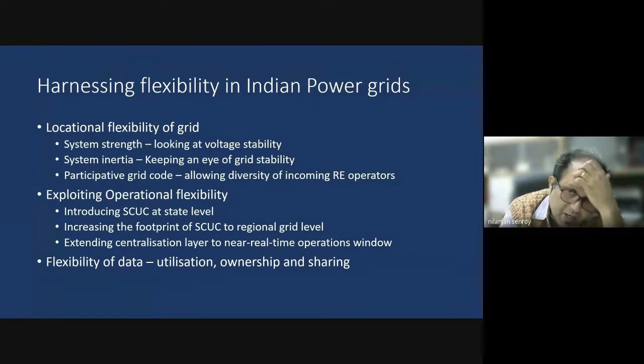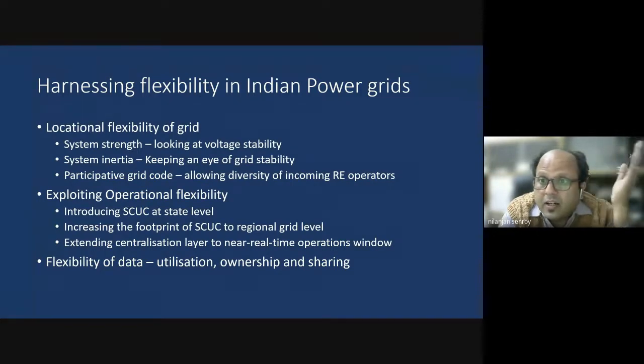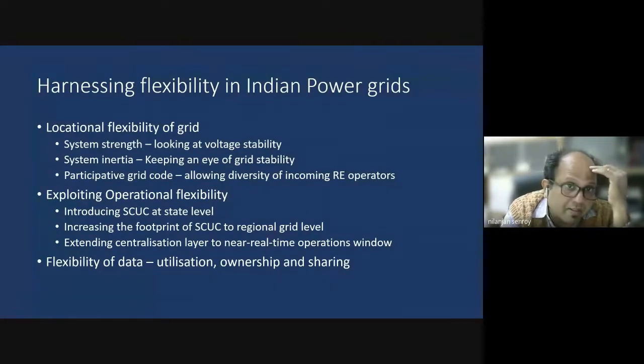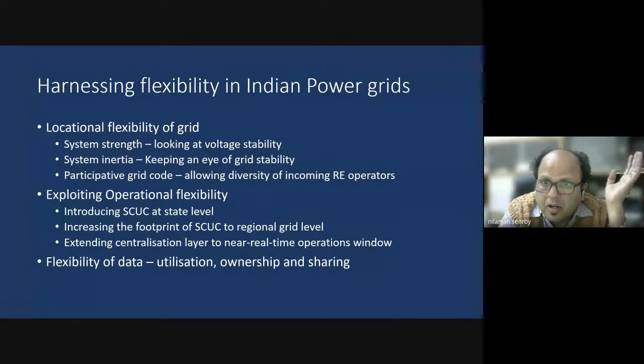Therefore, it is recommended that an accurate mapping of available system inertia should be carried out periodically, and you can reduce the scope of the problem by aggregating the grid into smaller areas that share similar inertial and dynamic characteristics. It is expected that within those areas, similar maximum RoCoF levels under various dispatch scenarios would be experienced. And finally, this may also help to update the settings of your frequency-based load shedding schemes, which respond to RoCoFs after a severe generation loss event.